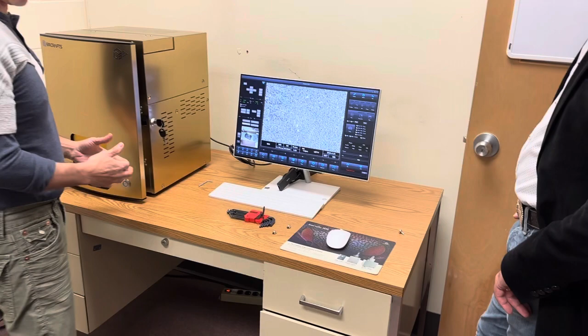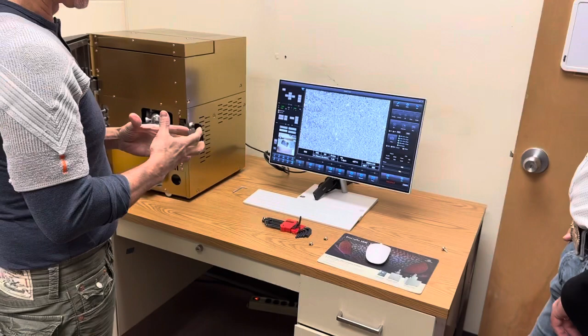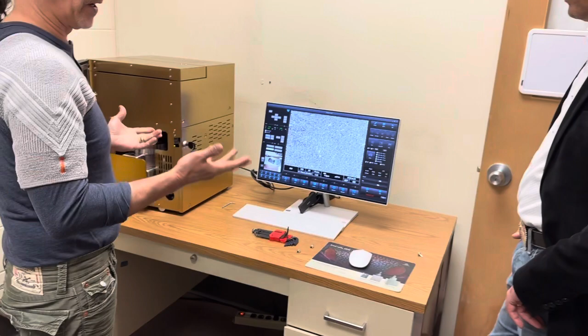The reason is there's a turbo pump inside here. This is our column, and behind it there's a turbomolecular pump with no fans cooling it. So if you left that pump going for two weeks, it might overheat and seize a bearing or something like that. Running it for 8 hours, fine, no problem, but it shouldn't stay on indefinitely.